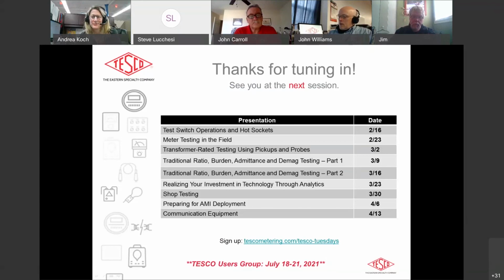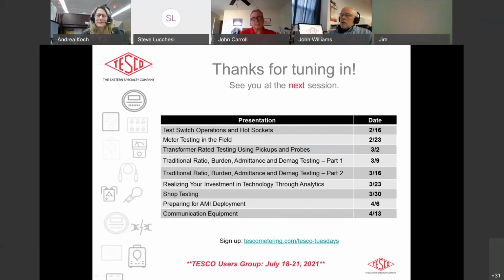So I've had to deal with in other situations with customers talking about how the CTs and PTs are managed, right? They're typically managed as assets. And under that asset control, especially some of the bigger utilities have a certain amount of rules and regulations as to how they're tested, how accurate they are, their applications. There's a lot of things that go into it, because all the way down to the programming of the meter, you have to have the right CT and PT factors in the meter.